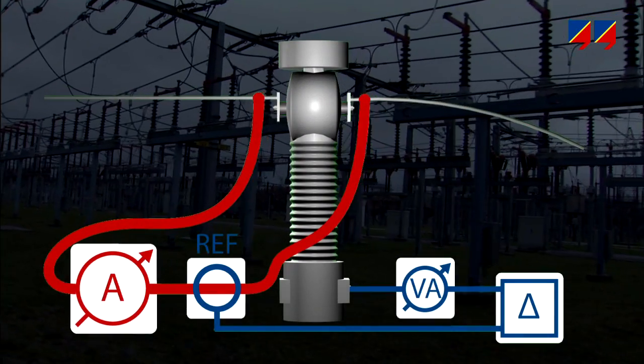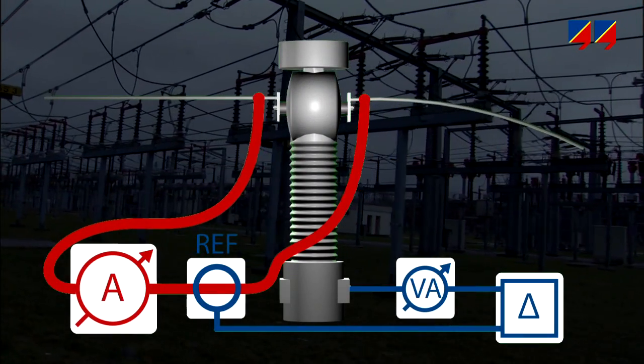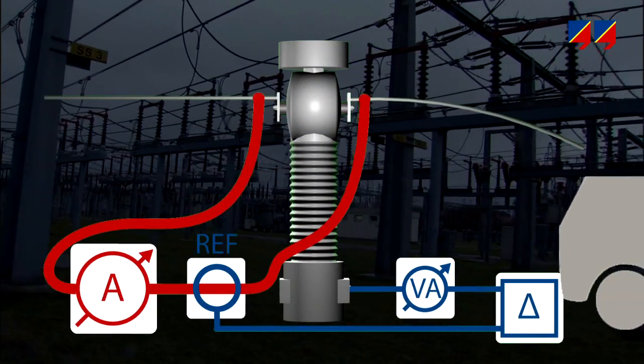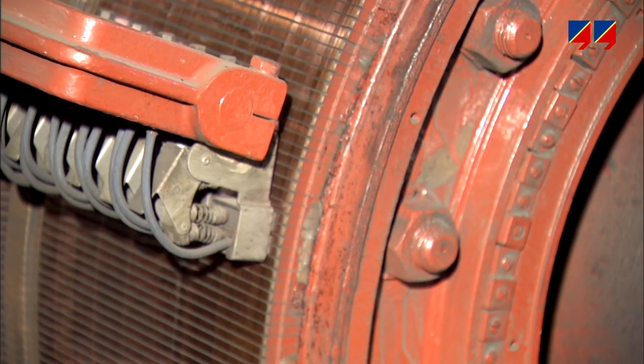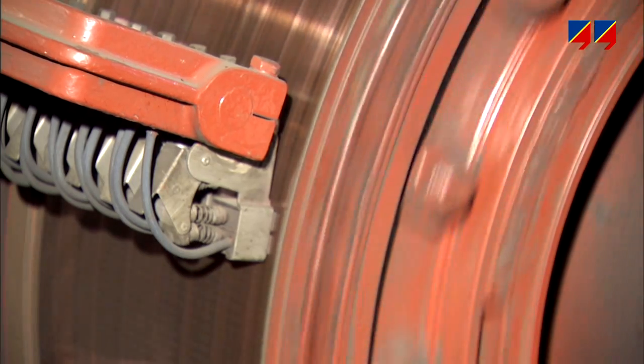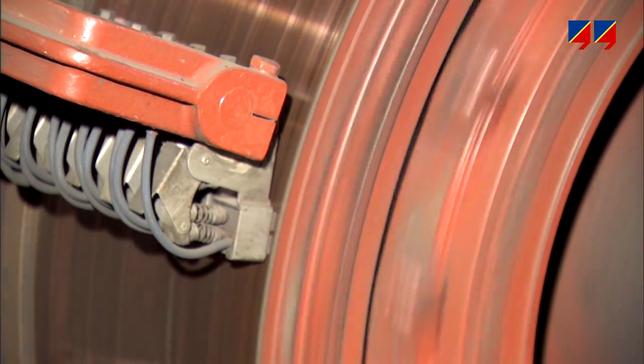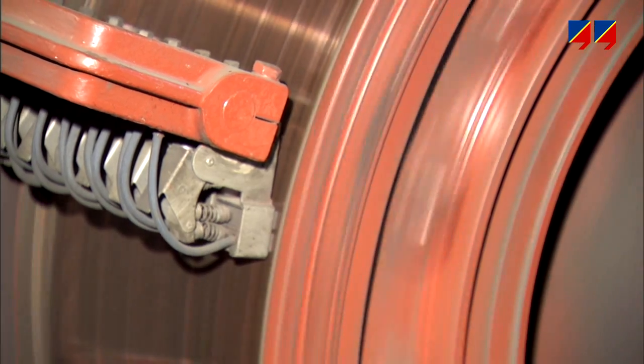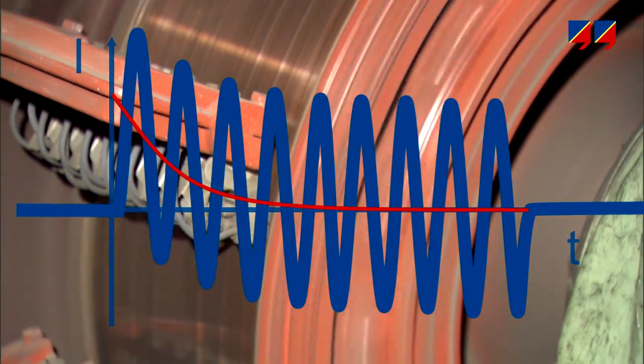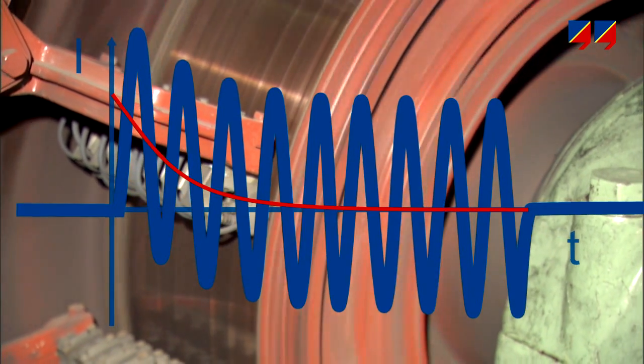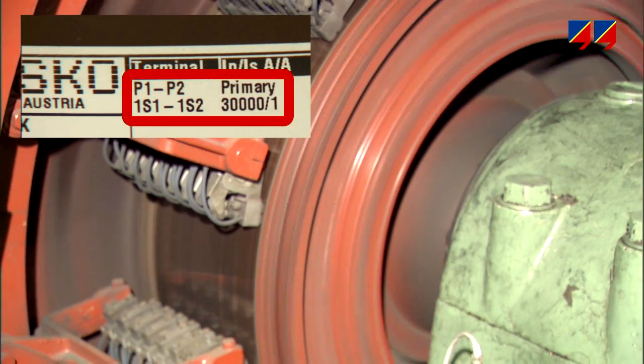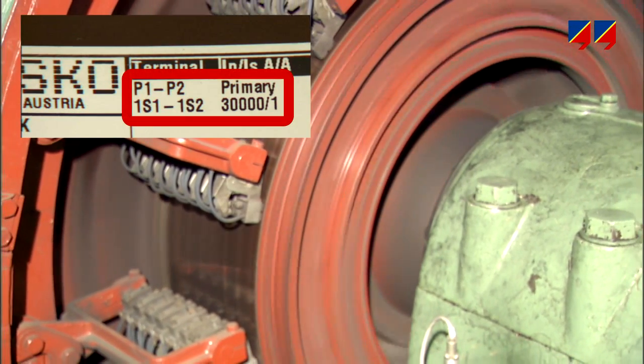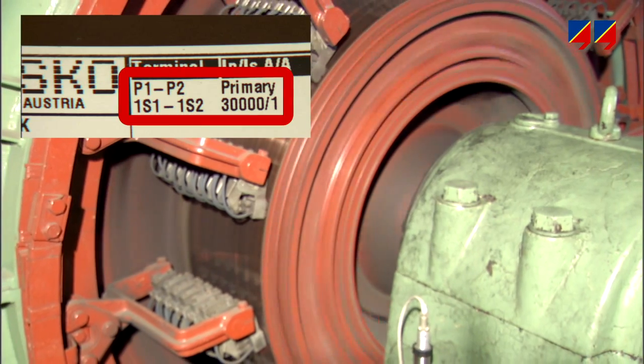This method is costly and laborious, particularly on site, as heavy components need to be shipped and unwieldy cables are required for the current injection. Even this method reaches its limits where protection CTs designed for high short circuit currents, high DC components in the fault current, or high primary time constants are involved. Such CTs require thousands of amps for testing them, exceeding the largest current source's maximum output current.